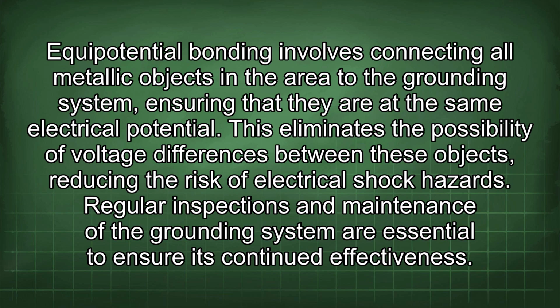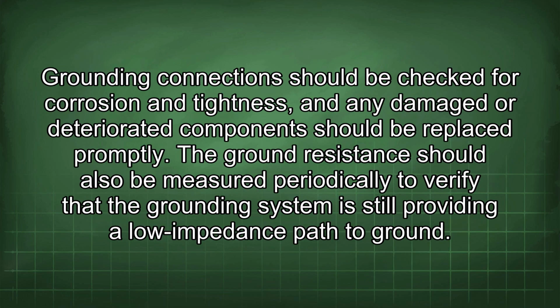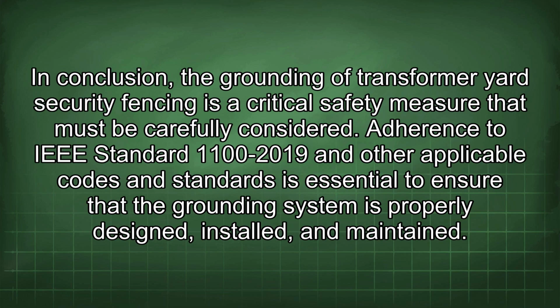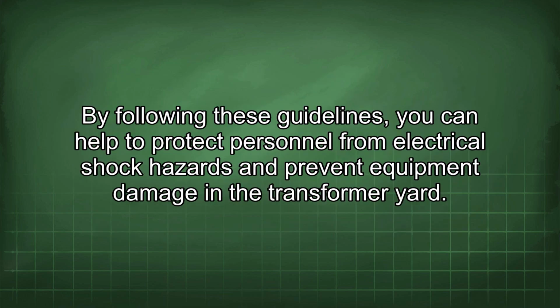Regular inspections and maintenance of the grounding system are essential to ensure its continued effectiveness. Grounding connections should be checked for corrosion and tightness, and any damaged or deteriorated component should be replaced promptly. The ground resistance should also be measured periodically to verify that the grounding system is still providing a low impedance path to ground. In conclusion, the grounding of transformer yard security fencing is a critical safety measure that must be carefully considered. Adherence to IEEE Standard 1100-2019 and other applicable codes and standards is essential to ensure that the grounding system is properly designed, installed, and maintained. By following these guidelines, you can help to protect personnel from electrical shock hazards and prevent equipment damage in the transformer yard.